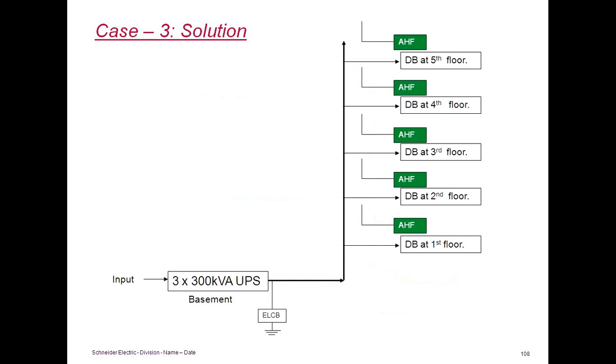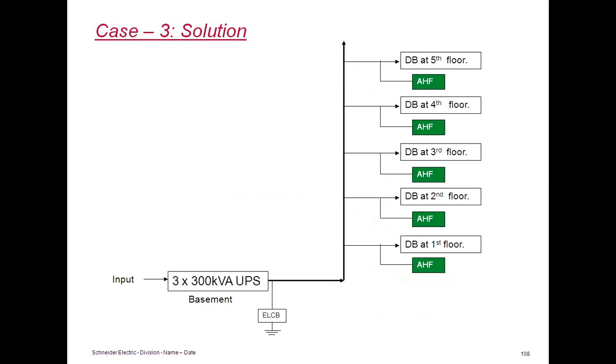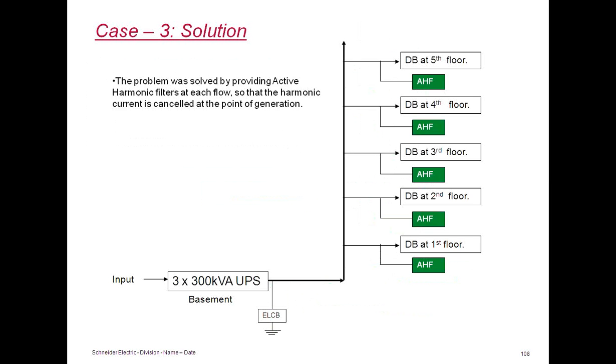The problem was solved by putting active harmonic conditioners at each DB level, each floor level. We made sure the harmonics are absorbed at each floor level, and no harmonics came out of the distribution board or cable. So the problem was solved. Till then, there has been no tripping in the breaker. It's safe. Yeah. So this is from my side, Mr. Manasa.